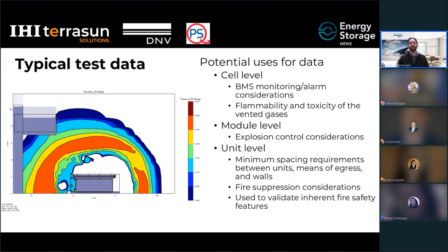And further down the line, the unit level tests can help us evaluate minimum spacing requirements, egress paths, distance from walls and flammable materials within the container as well. So these allow us to support different fire suppression considerations to evaluate their effectiveness. And also allows us to take a look at the overall configuration of the BESS unit and how it's best laid out, including the location of fire detection and suppression equipment.